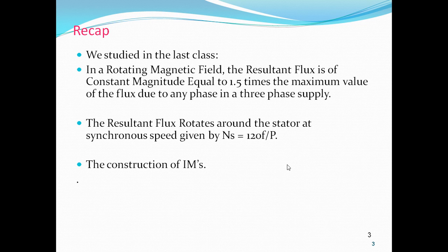When the three-phase supply is given to the stator winding, as we are seeing in the slide also, a rotating magnetic field of constant magnitude is produced, which is rotating at synchronous speed, and the resultant flux is equal to 1.5 times the maximum flux. This is at any instant. This rotating flux induces an EMF in the rotor by the mutual induction principle.